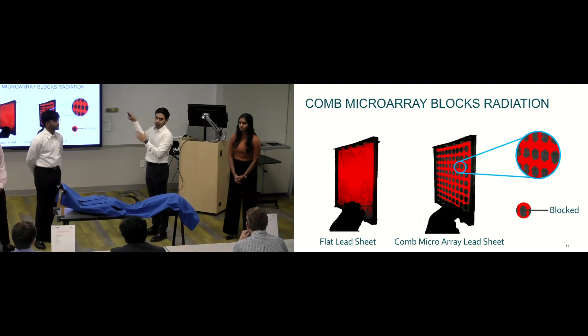The main utility of this pattern is that because you have this pattern on the surface, you're removing some lead from the surface. And because you're removing lead, you can reduce the weight by at least 25%. Also, we are increasing the surface area present on the top of the surface, thereby increasing the number of X-ray interactions and more absorption. And then these two pieces of technology come together to create 30% more effective shielding for the clinicians.